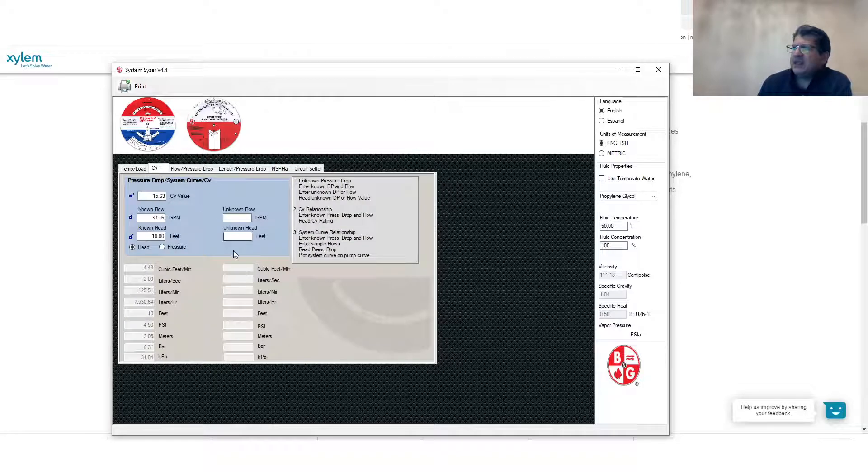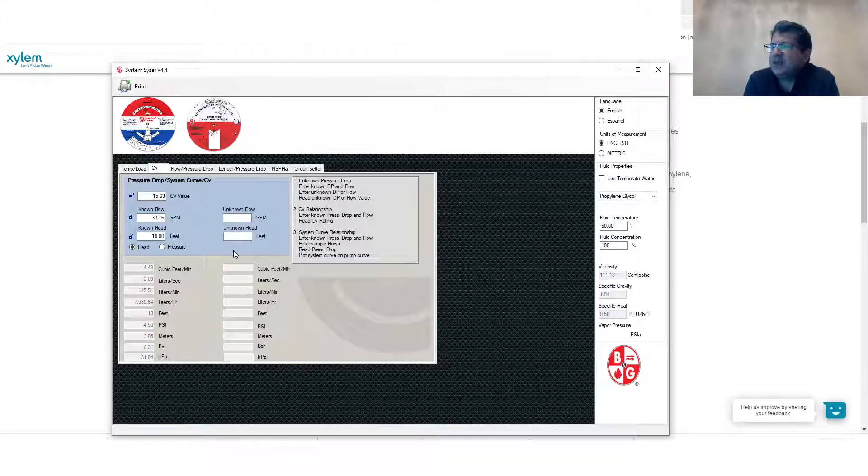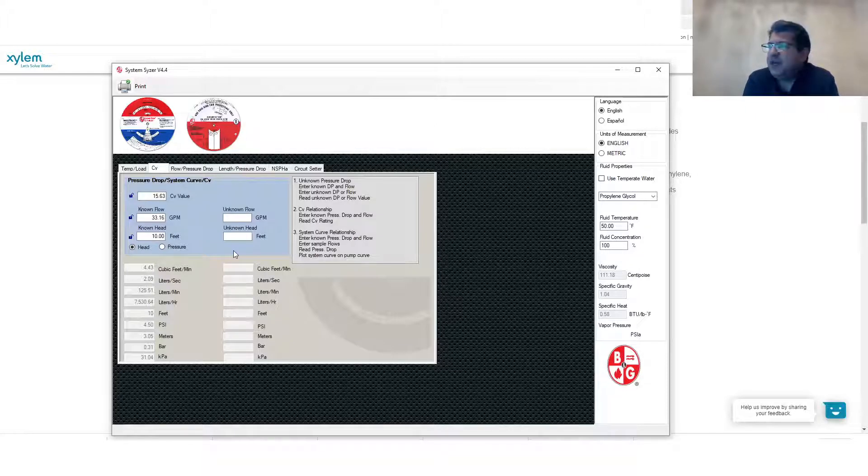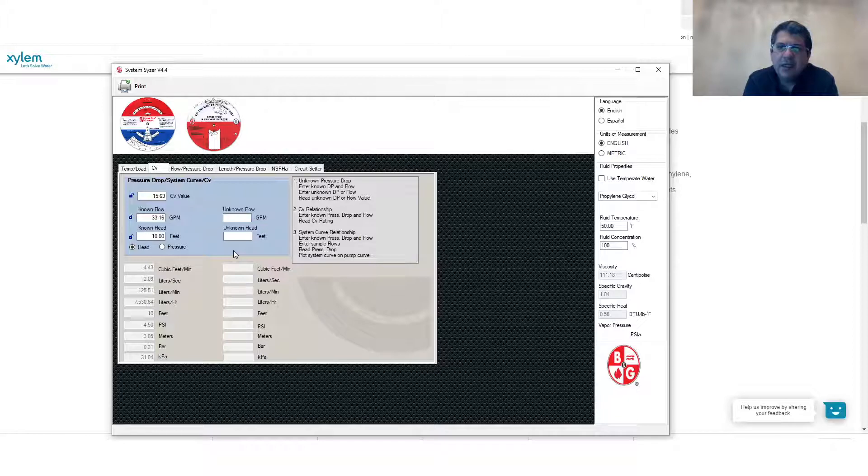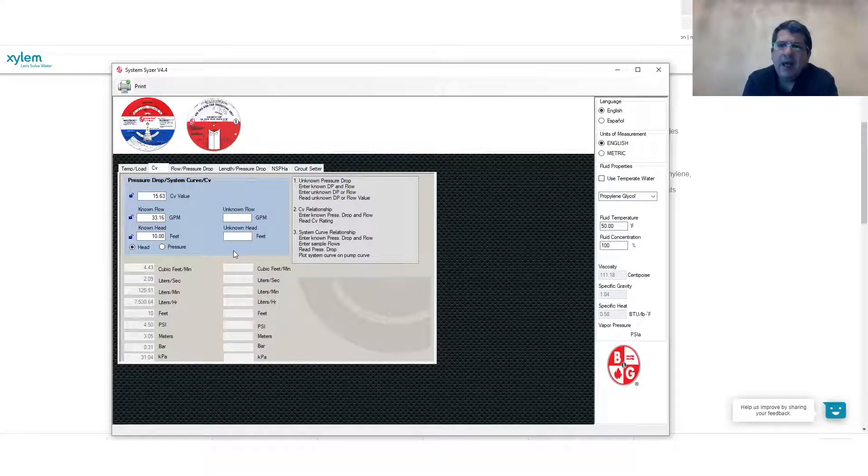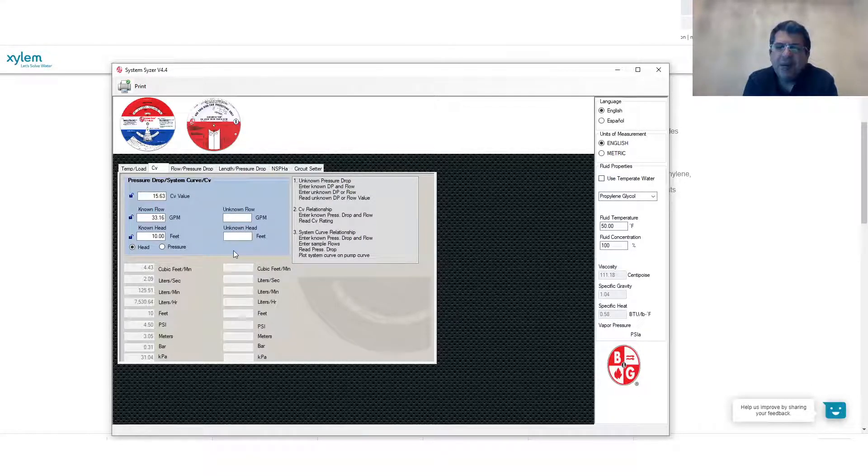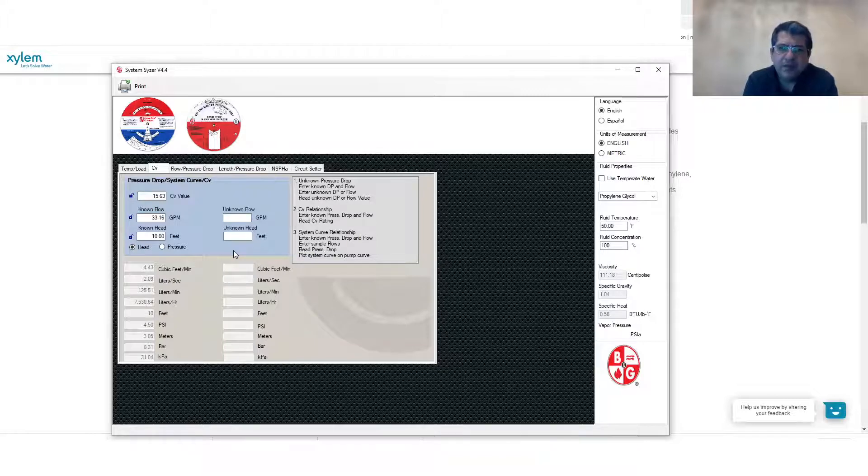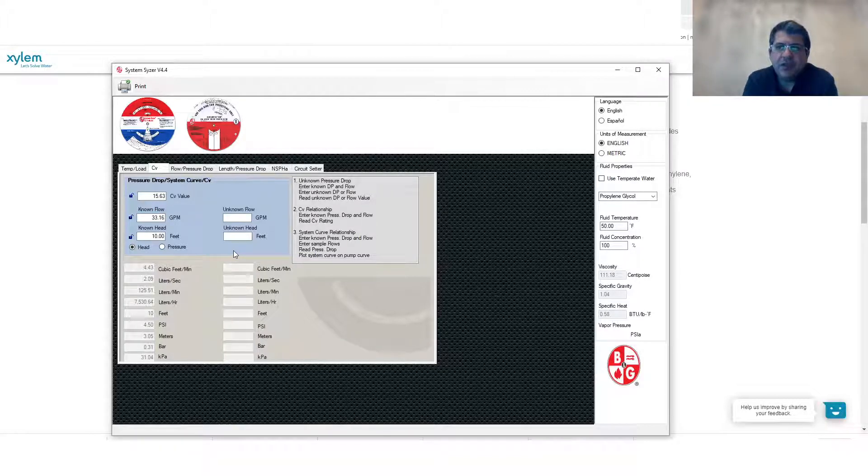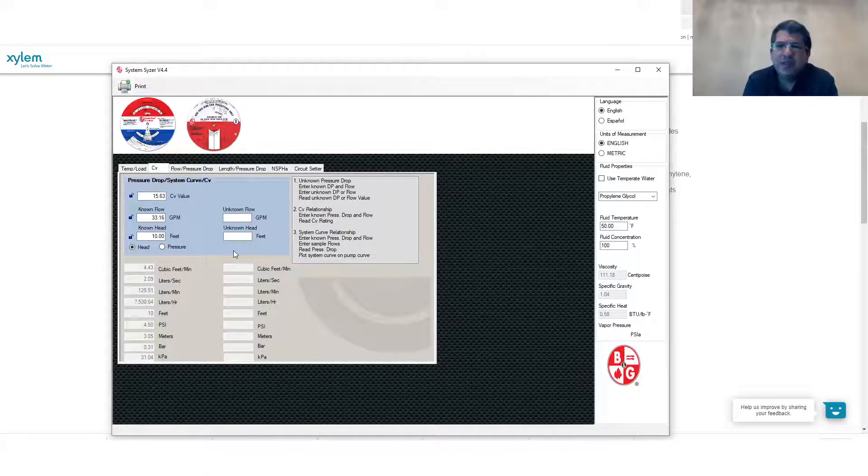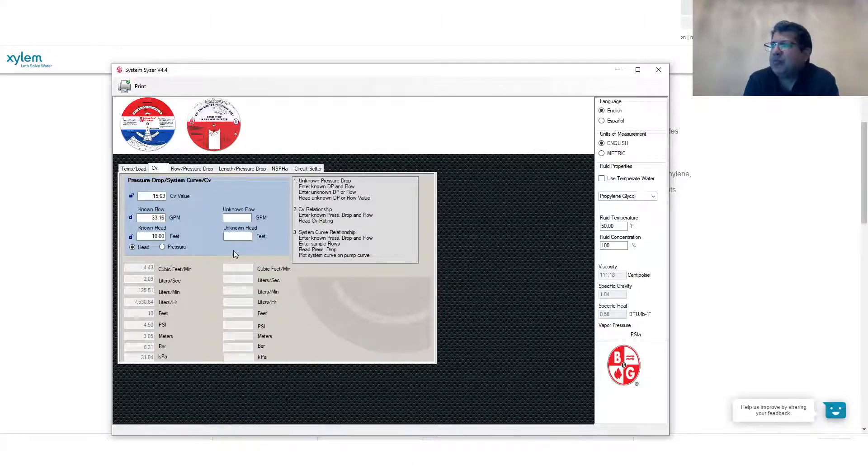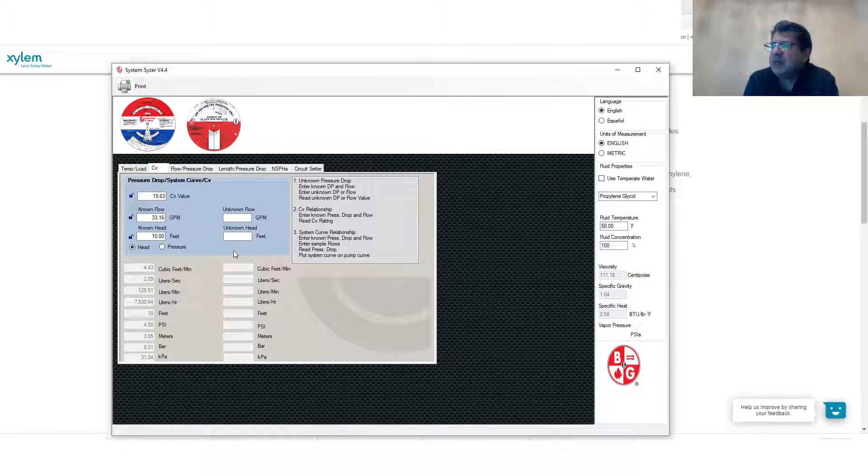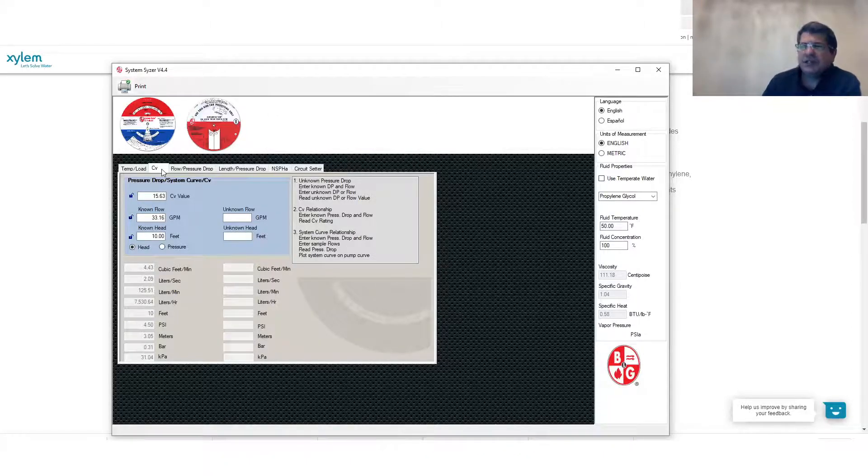On the second tab, the CV can be calculated here based on different GPM and different CV, you can get the total head and vice versa. This is very helpful where you can build your system curve. When you're selecting a pump, you can cross reference between the system curve and the pump to understand what's your duty point and what is your capability of the pump. Would it be a good choice to handle your system? For the hydronic you need to distribute into your system as a whole. That's very handy for you to be able to build the system curve because you can plot multiple CVs between the pressure drop in form of head and the GPM. So you can build the system curve with this tab of CV.